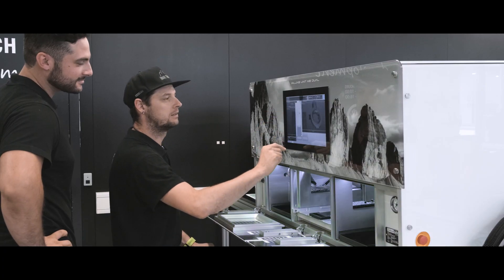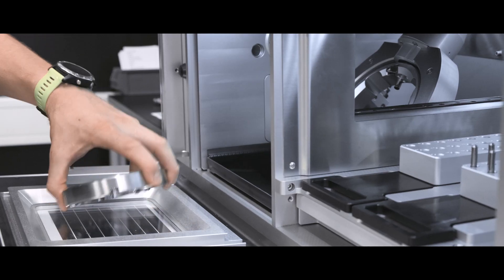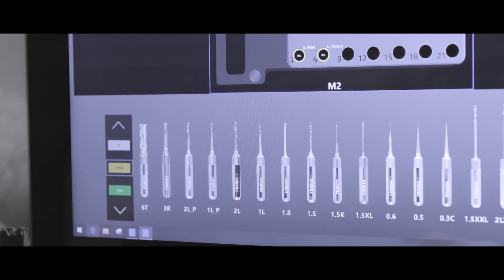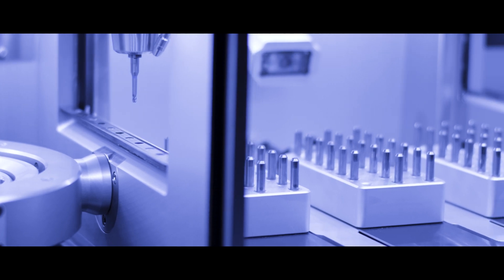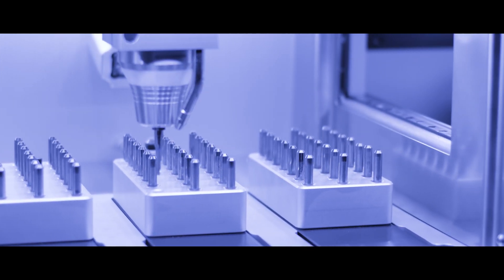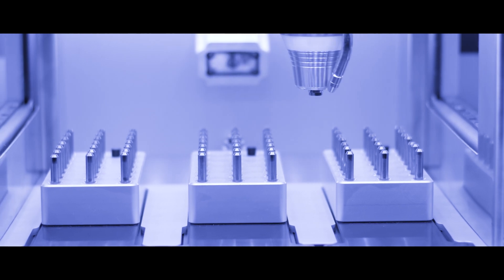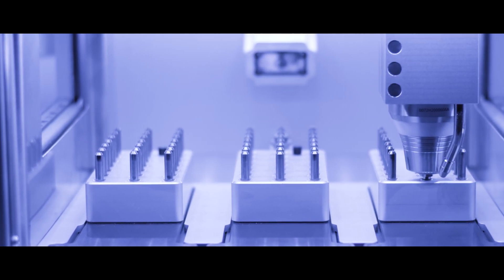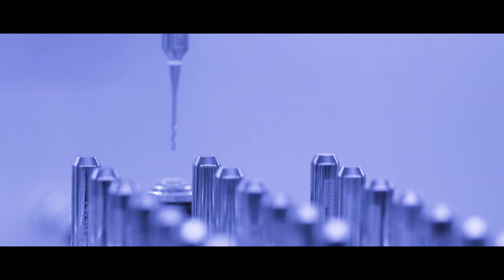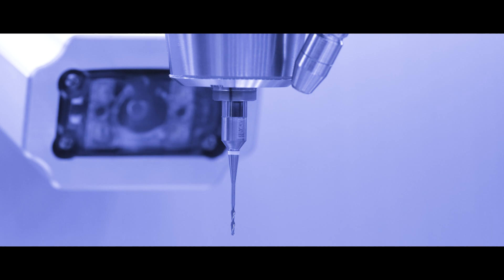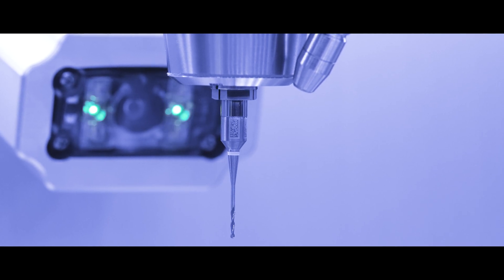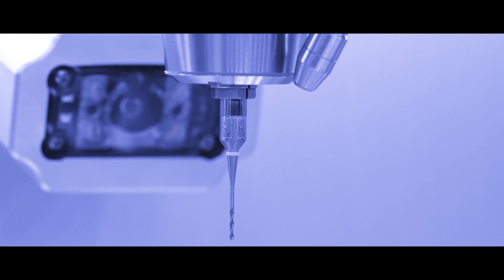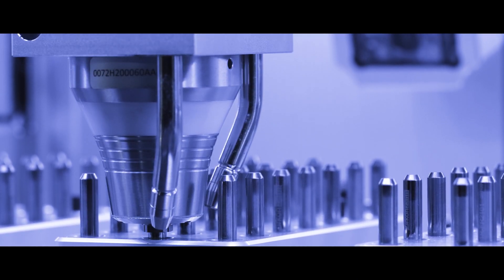With the integrated touch screen, the user can not only select material blanks and burrs through the drag and drop function, but also start the milling process and check whether the automatic tool changer and the optical tool detector work properly. In addition, a special camera detects and checks the burrs via a QR code. This functionality ensures the right selection of milling burrs before each milling cycle.